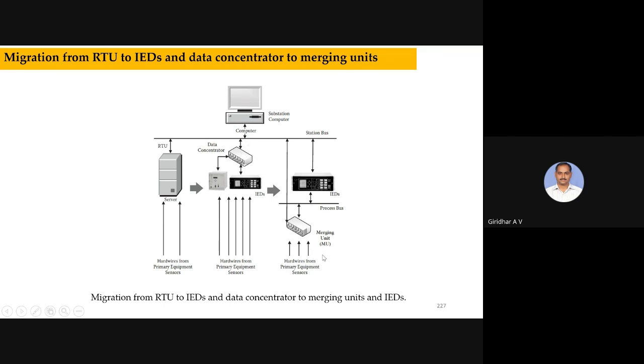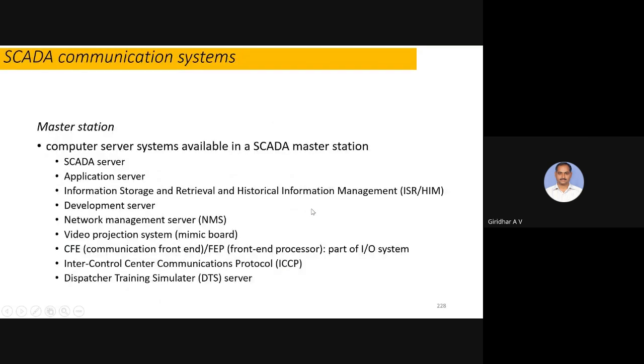Now through the process bus also, merging units convert all the data into digital data, and it is processed straight away to the station bus through the process bus. That is how they are doing communications. Even if you want to do protection, with IEDs connected to this process bus, appropriate control actions will be given. Not only control, it will also have a protection feature. In that way, there are more advances in this. Even fault diagnosis will be there.